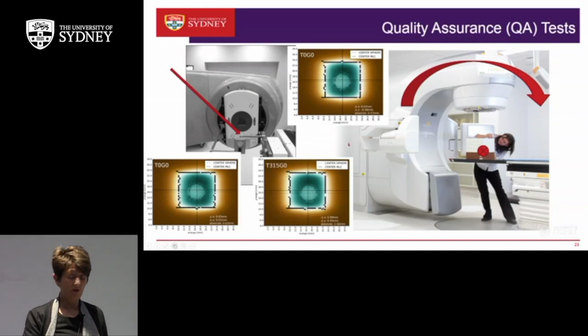If we move the gantry around to another angle, we shoot another film, and so we can see this is what we call the isocenter run out, and that can tell us how big that sphere is that the gantry is rotating in space. And in this case, it's better than 1 millimetre in all cases.